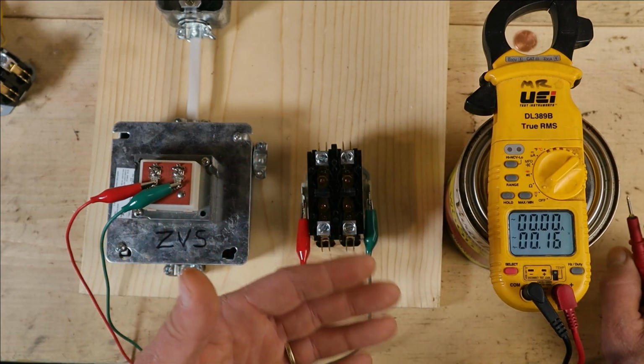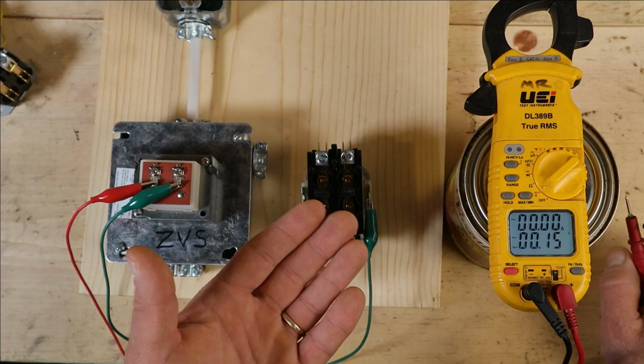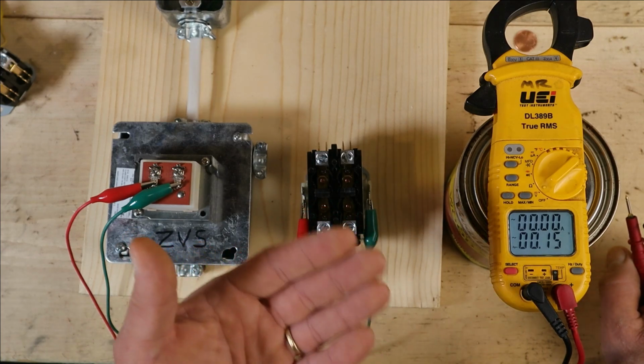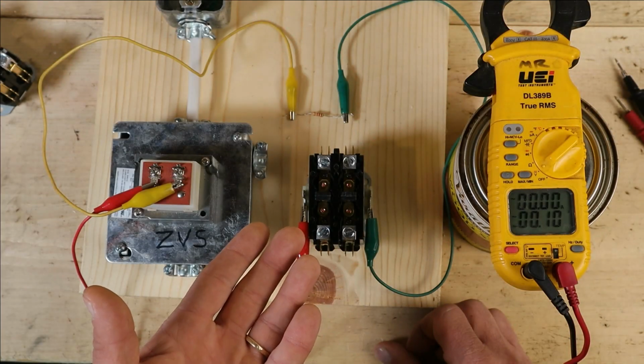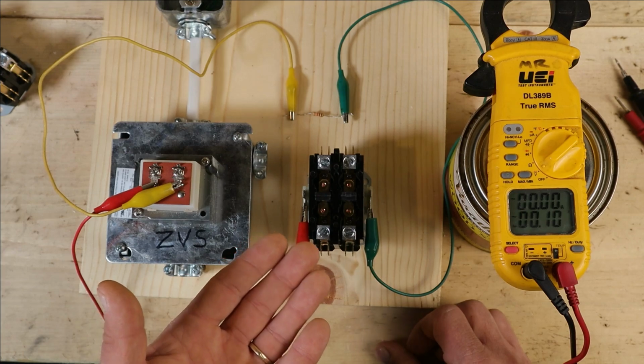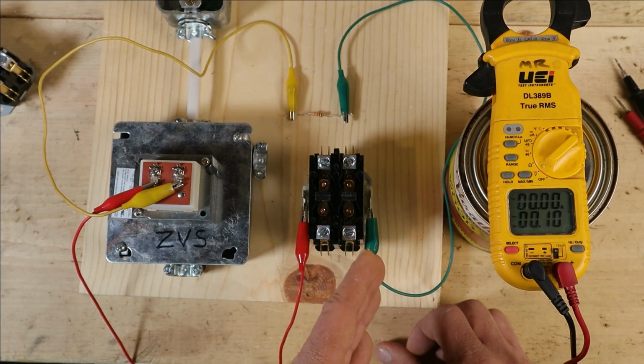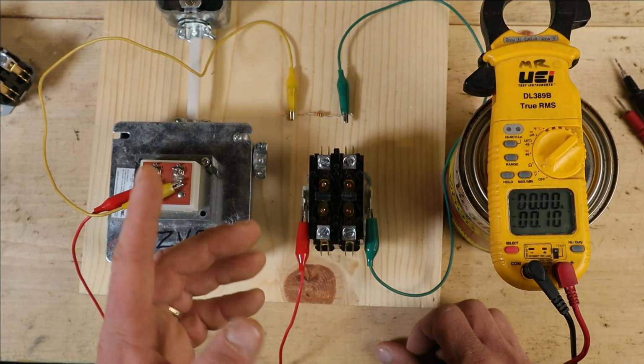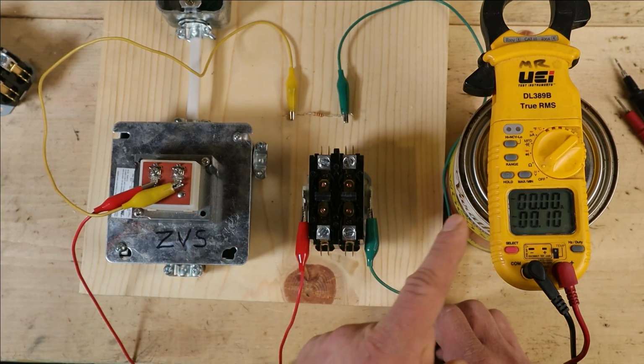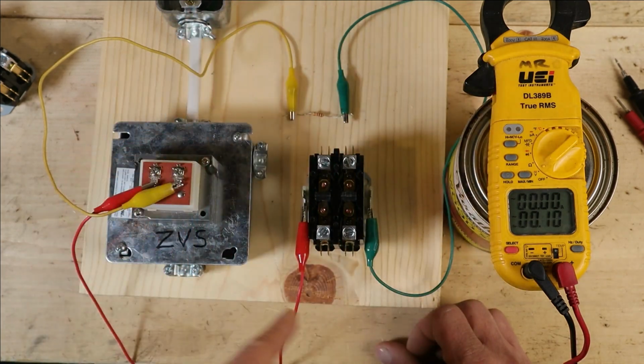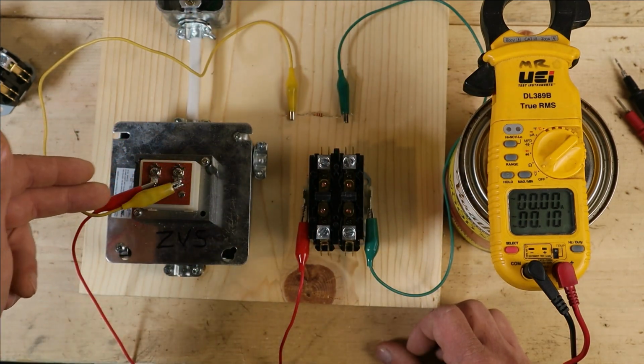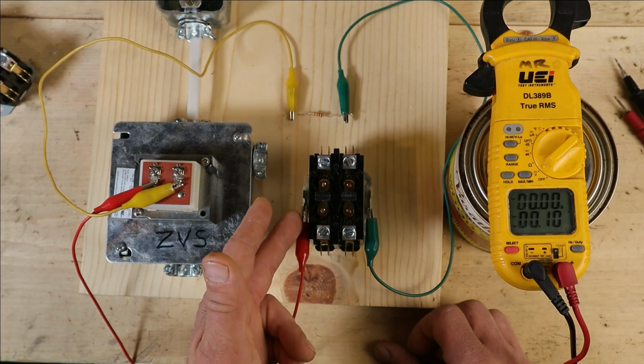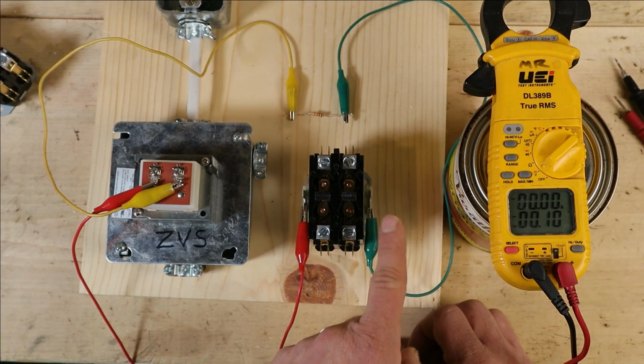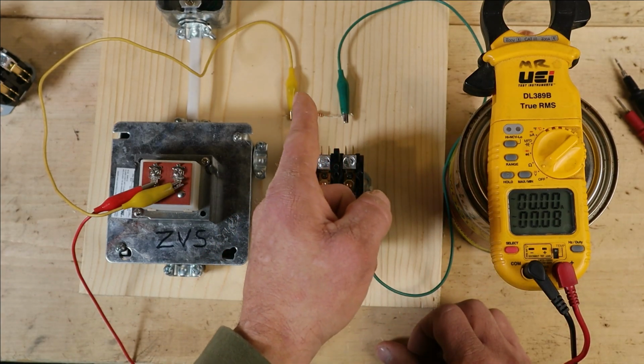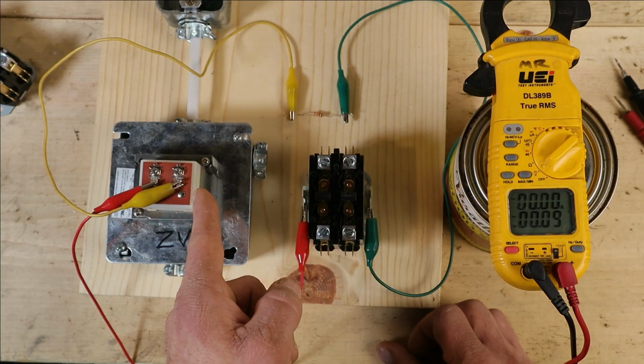Now let's see what happens when we put these two components together into a circuit that's wired in series. Now what I mean by a circuit that's wired in series is that each component in this circuit is wired one after the other. So the electricity has to flow through each component one at a time to complete the whole circuit. So we can see we have 24 volts coming off our transformer, one side of the coil, coming out the other side, going into our resistor, leaving the resistor, and coming back to common on the transformer.